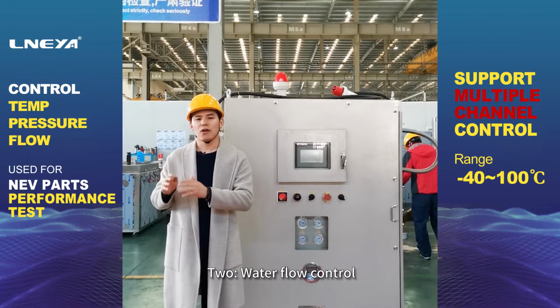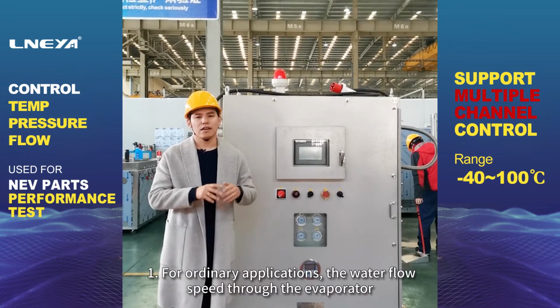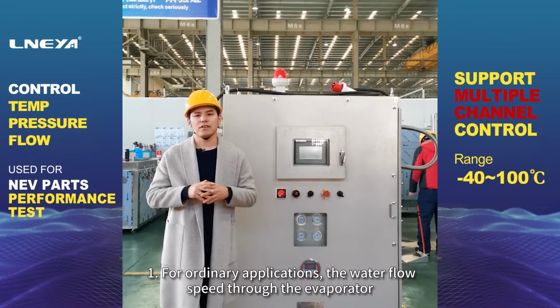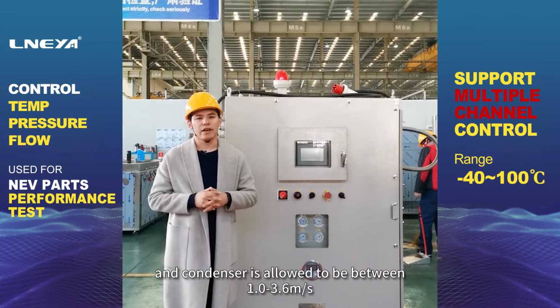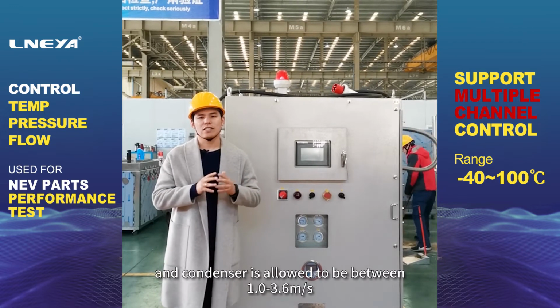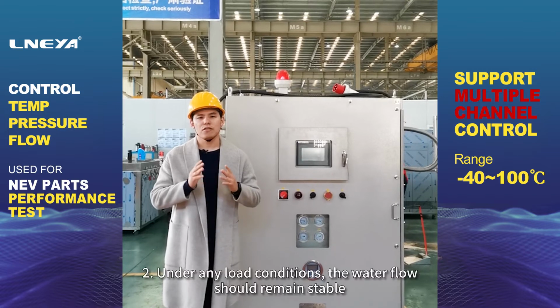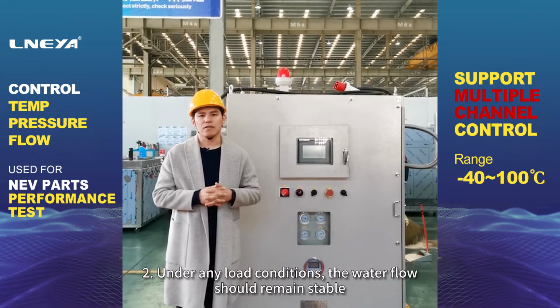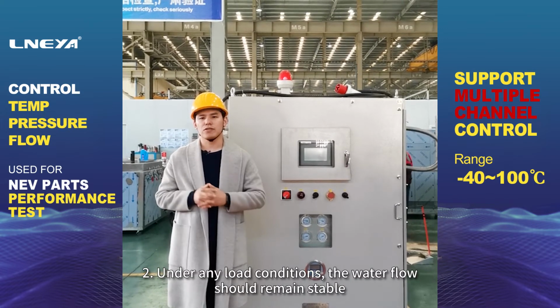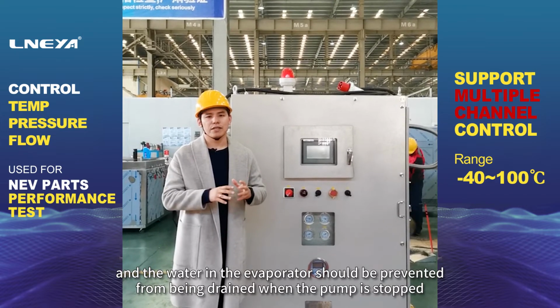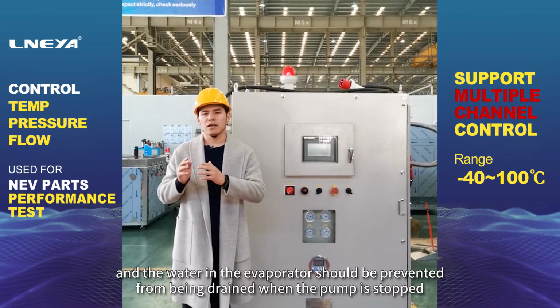2. Water flow control. First, for ordinary applications, the water flow speed through the evaporator and condenser is allowed to be between 1-3.6 m/s. Second, under any load conditions, the water flow should remain stable, and the water in the evaporator should be prevented from being drained when the pump is stopped.